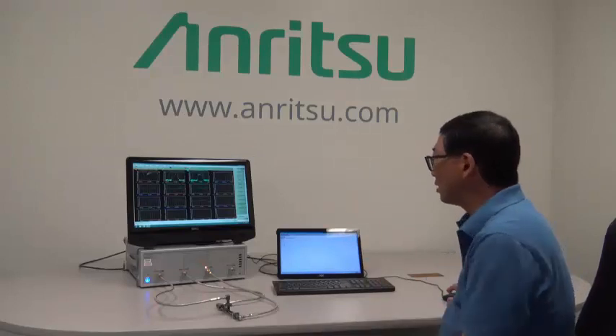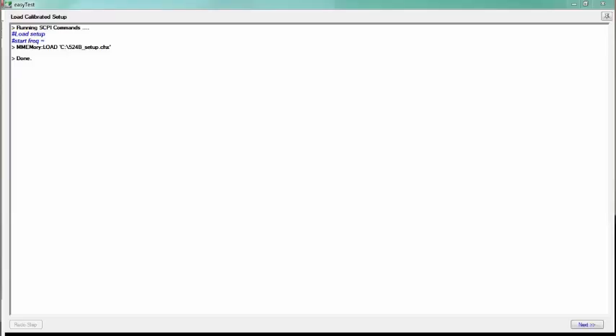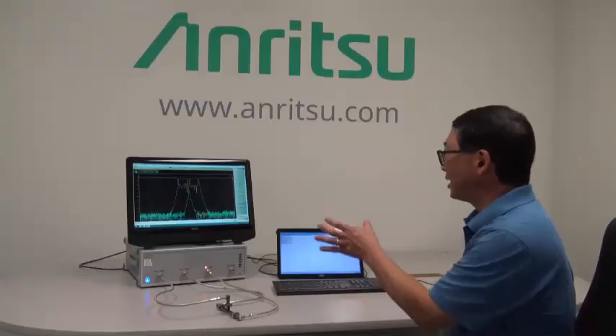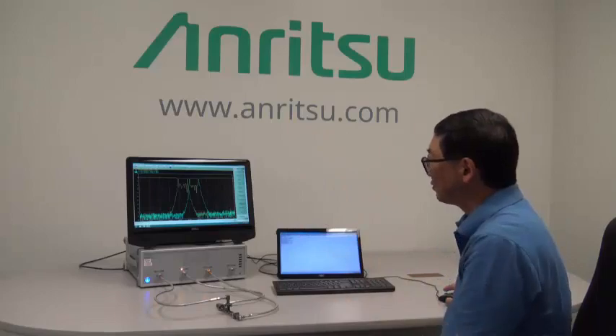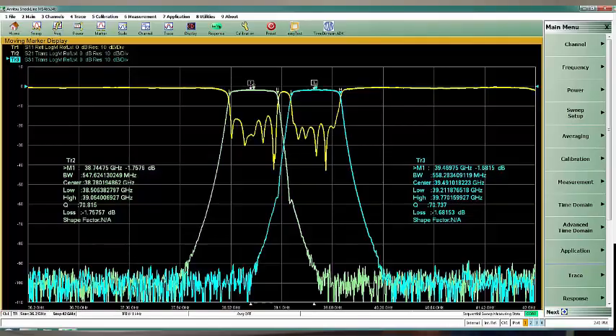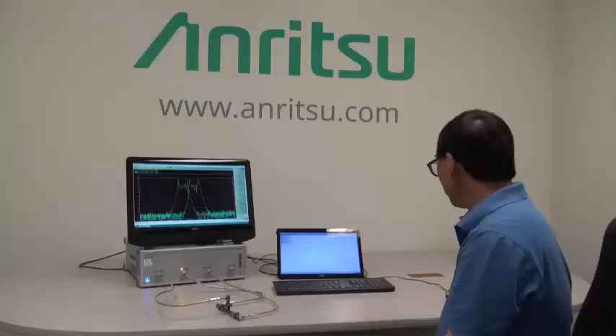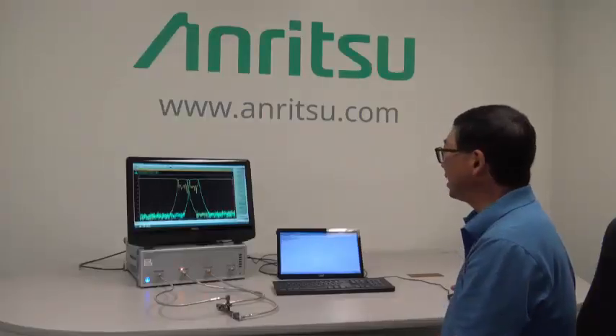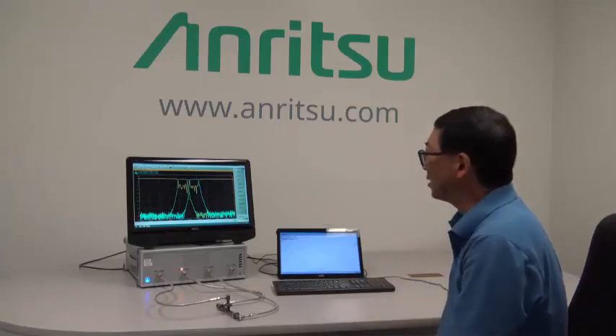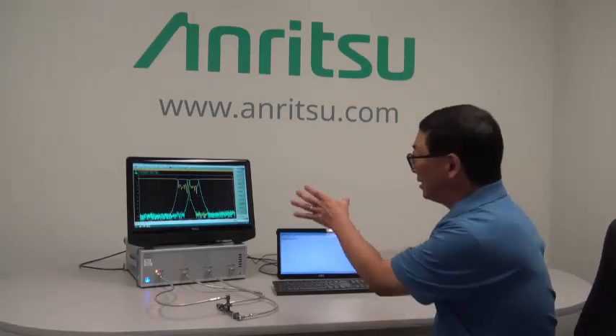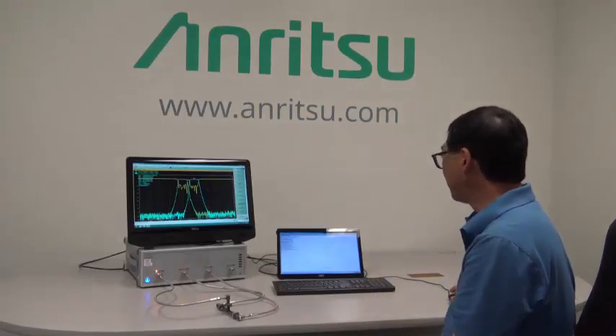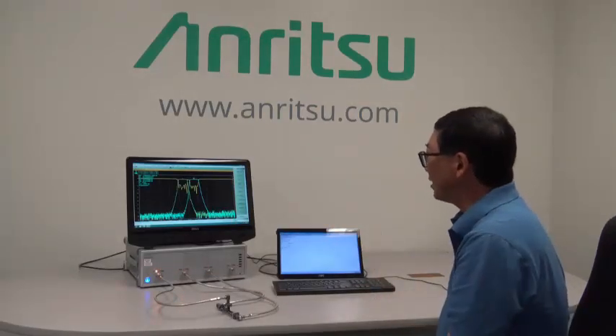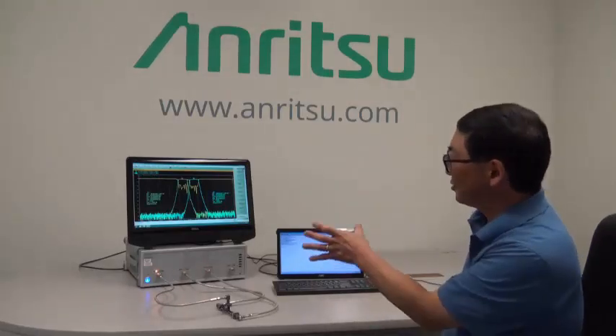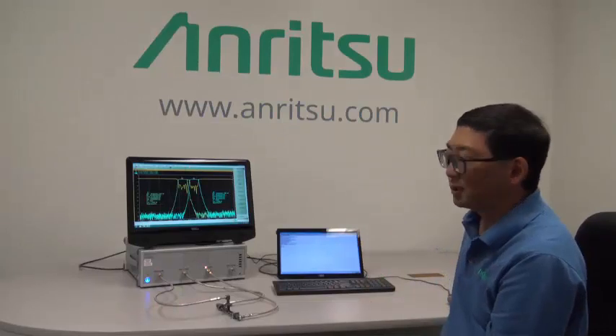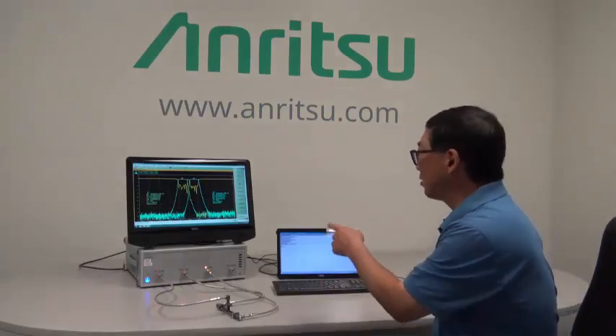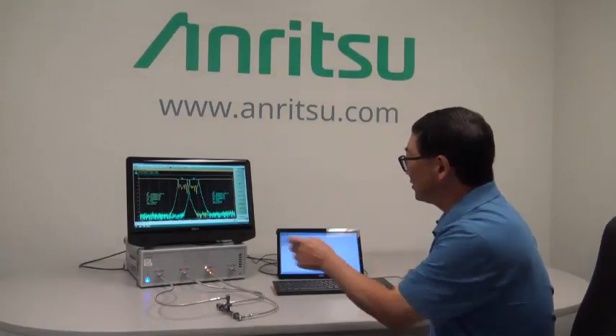So here we're recalling a setup that I have stored on the VNA. Setting up the graphics on the screen so that we have 3 traces, S11, S21, S31 on the same display. We also have the ability to make it brighter, so we've thickened up the traces here and increased the font size, to make it a little bit easier to see for the user. Here we've added markers, and we can reposition the data such that it's easier to see. We've added bandwidth search so that the 2 markers show the channel bandwidth of each side of the diplexer.